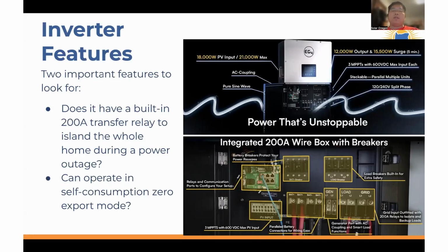So you need to find one that does, and these all-in-one hybrid inverters typically come with one. But if you want to back up your whole house and not do a sub panel, you need that transfer relay to handle 200 amps, which is the typical main amperage or power feed that most homes have from the grid.